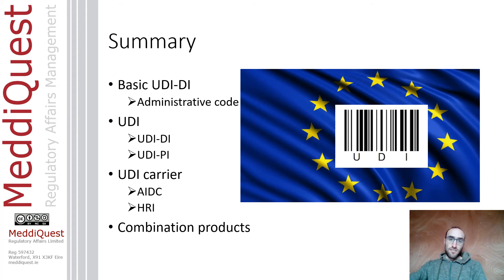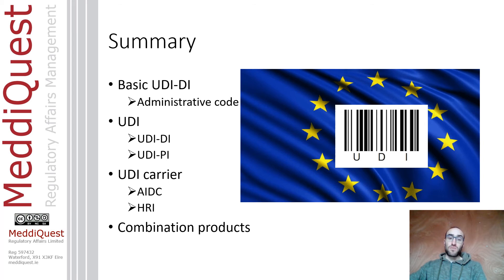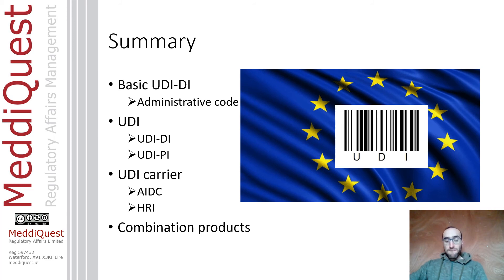To summarize: the Basic UDI-DI is an administrative code used to identify the manufacturer and group devices of the same category. The UDI is composed of the UDI-DI, a fixed part obtained by registering with an official entity, and the UDI-PI, the dynamic part related to production. The UDI carrier has two parts: AIDC for automatic scanning and HRI for human readability. For combination products regulated as a medical device, UDI is required; if regulated as a medicinal product incorporating a medical device, UDI is not mandatory.